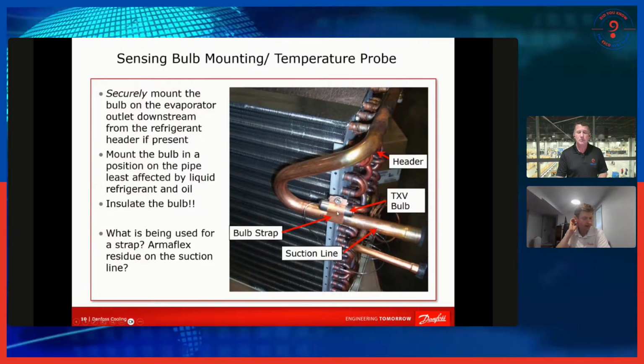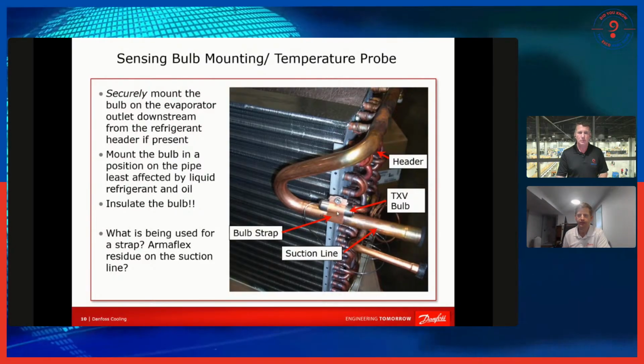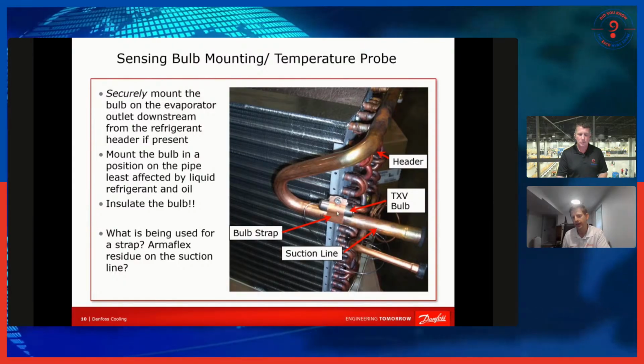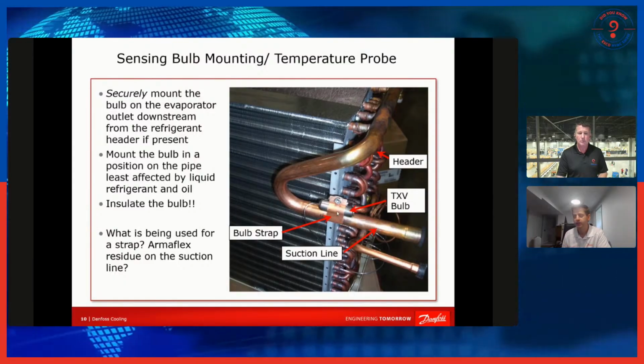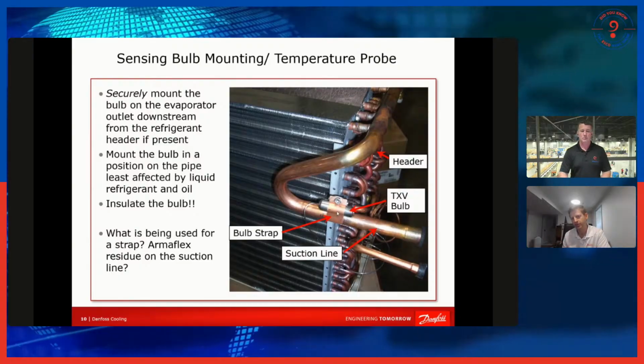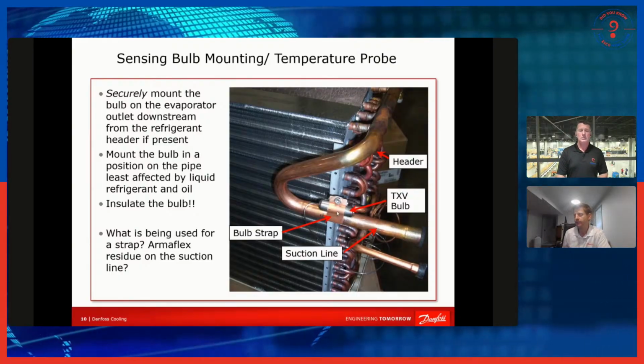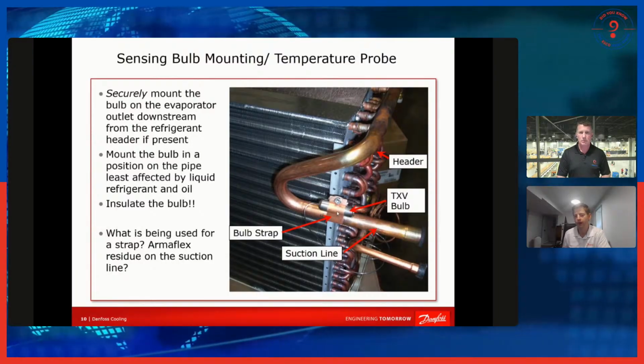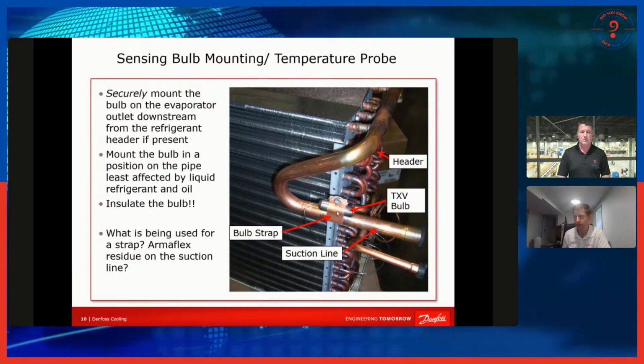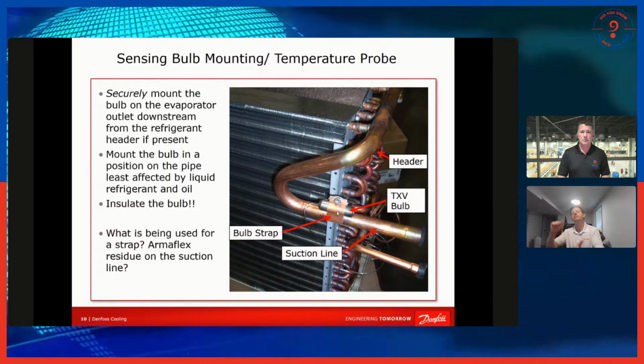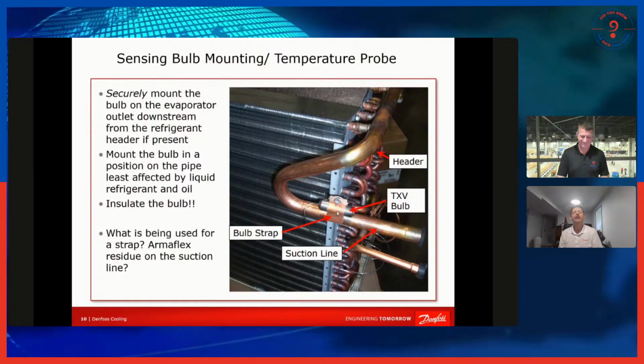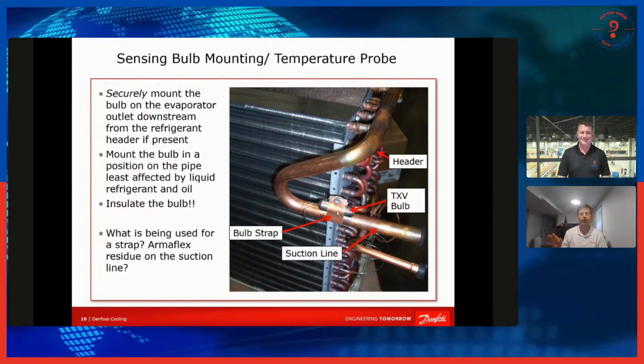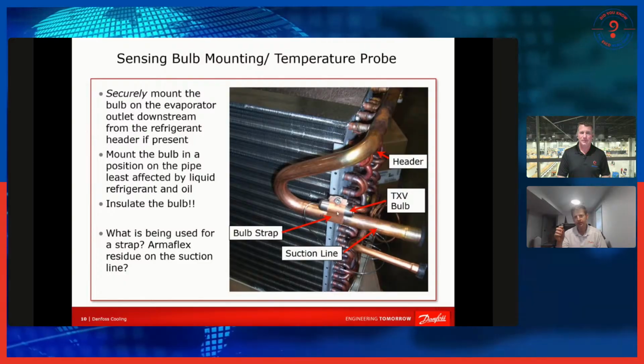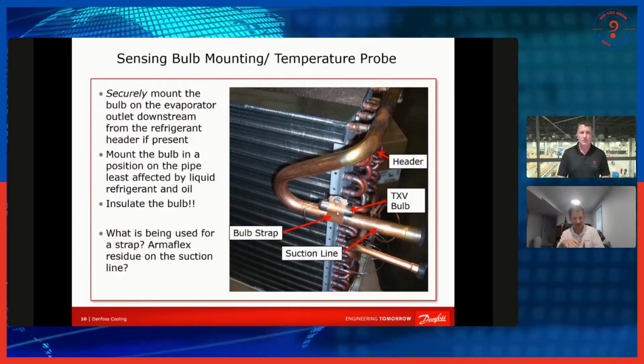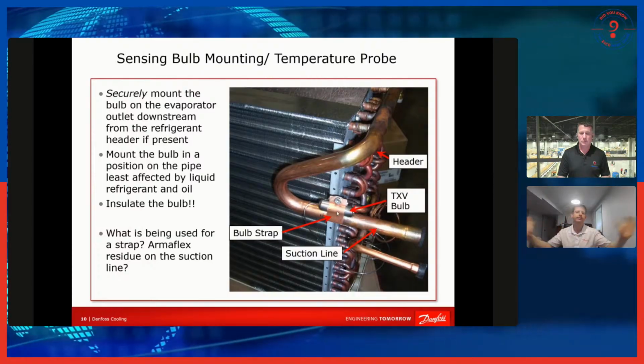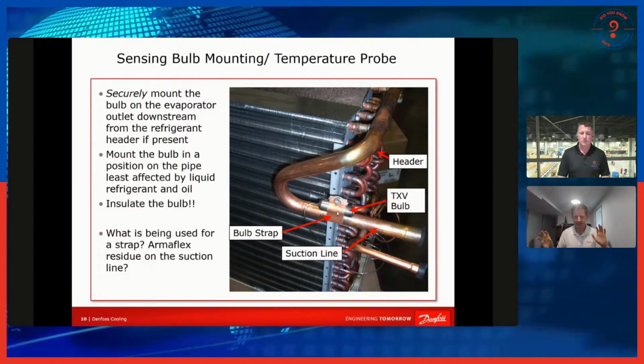When it comes to a temperature probe, a lot of the same things. You prefer to have something stronger and more rigid than a zip tie. It's better if it's insulated. That helps it to get a better sense of the temperature. And when it comes to troubleshooting, especially with a system that's been around for a while, I always warn people to look for Armaflex that's been peeled away and you get that black gunk. If you have a TXV bulb or an EXV temperature probe that's on top of that gunk that's still left behind when you peel away Armaflex, that TXV or EXV is toast.